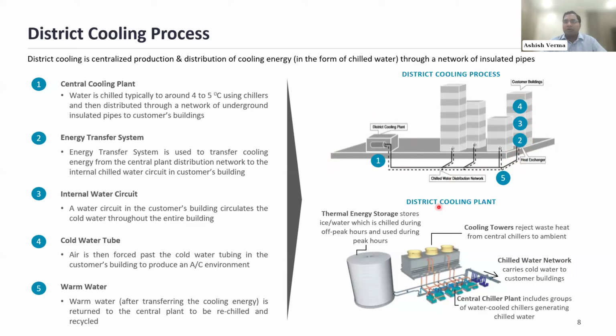There are multiple components here. The major component is the chiller, which is the major equipment that generates chilled water, the cooling medium. Chillers are associated with cooling towers, which dissipate heat into the ambient, because the heat gained from the buildings has to be dissipated somewhere. That heat goes into the environment, which is what happens with most air conditioning equipment. They gather heat from the indoors and reject it to the outside world.